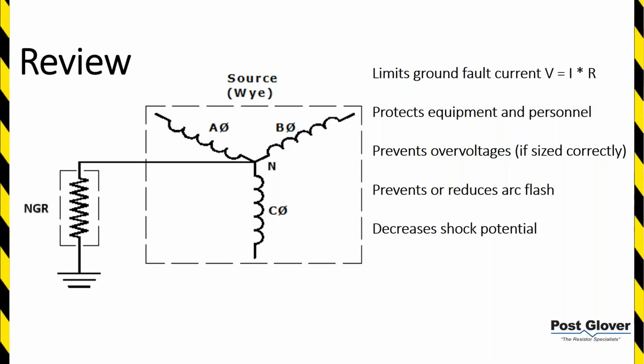Two typical values would be for a low resistance ground system, like 100 amps, 200 amps, 400 amps, in that range. There's variants, but those are probably the most common. High resistance ground, another topic, what we're going to talk about today, usually going to be 10 amps or below. Sometimes you get a little bit above that, but not normally.